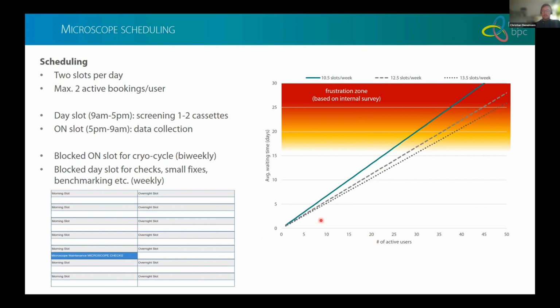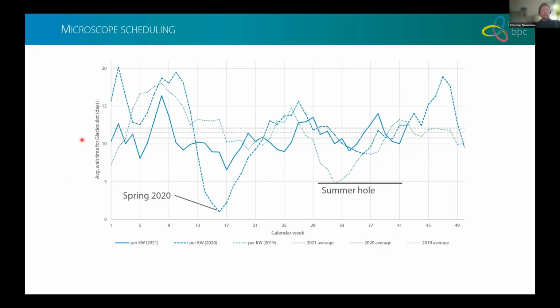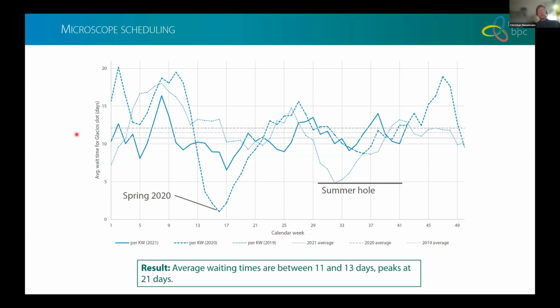That's the theory. The reality looks more like this. This is the average waiting time per calendar week over the last 3 years, or almost 3 years, on our Glacios machine. You see they fluctuate quite a lot. You see spring 2020, where nobody was in the lab to use the microscope. You see a summer hole, which is usually vacation time. But the average waiting times are well between 10 and 15 days, which corresponds to our 20 to 25 active users. So as a result of this type of scheduling, we got waiting times down to 11 to 13 days, with some peaks, but they happen rarely.